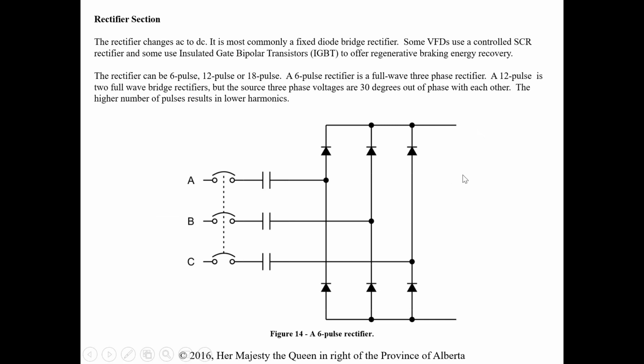So the rectifier section, again, changes the AC to DC, most commonly a fixed diode bridge rectifier. Some use an SCR rectifier, so a controlled bridge rectifier, and some use insulated gate bipolar transistors, or IGBTs. Those offer regenerative braking and energy recovery. So the rectifier can be 6 pulse, 12 pulse, or 18. A 6 pulse is basically a 3-phase rectifier. A 12 is 2 full wave bridge rectifiers, but the source voltages are 30 degrees out of phase with each other. The higher number of pulses results in lower harmonics.